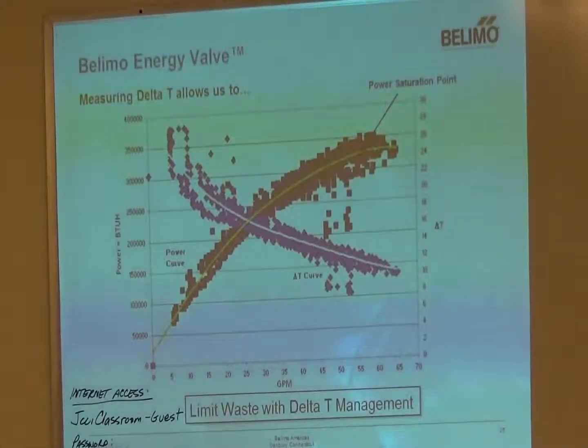So, as Brian was mentioning with the delta T manager, that's one of the settings in the valve. You can say, this is the delta T I want to achieve. Once the valve sees you're at that delta T, if you drop below it, the valve will take over from the building automation system and say, we're not going to allow any more flow through this coil. As we talked about in the other formula earlier, delta T and flow are inversely proportional, so more flow will cause more of a decrease in delta T. We won't allow that to happen.